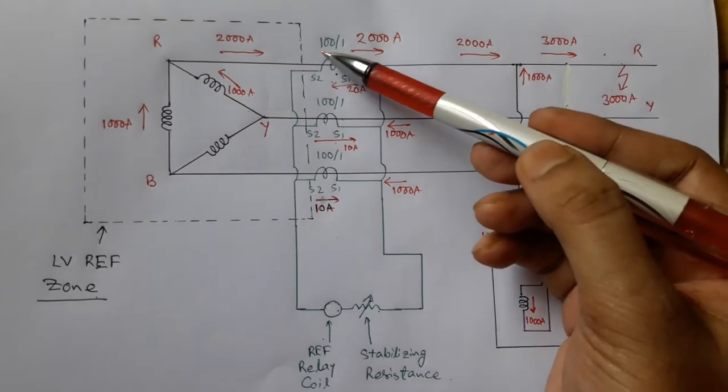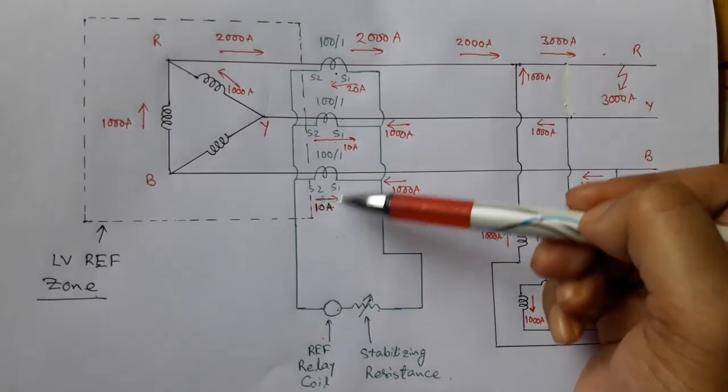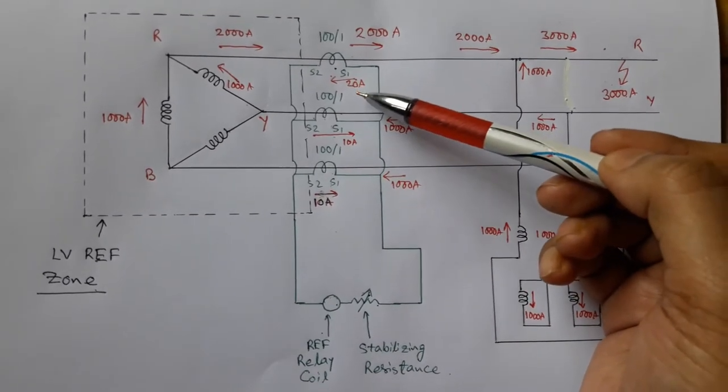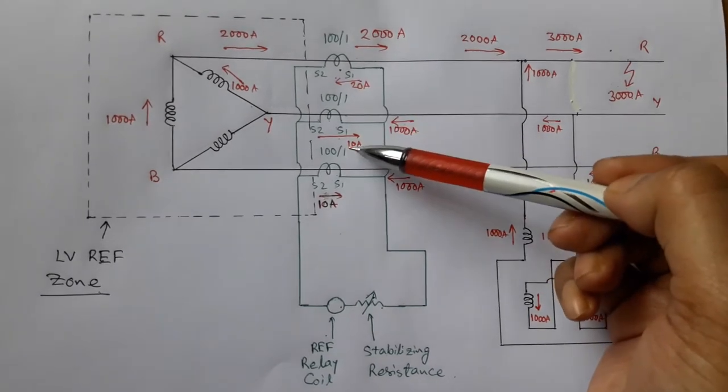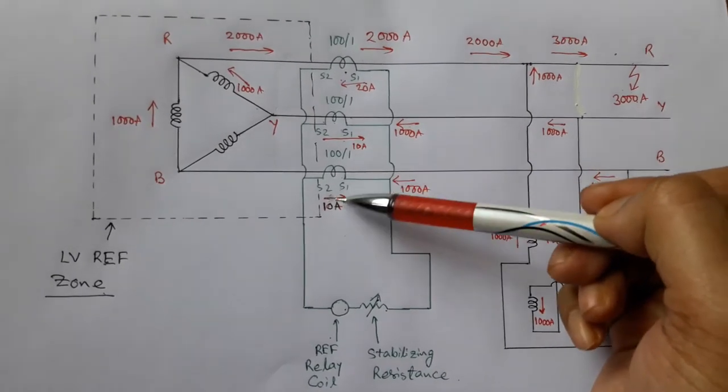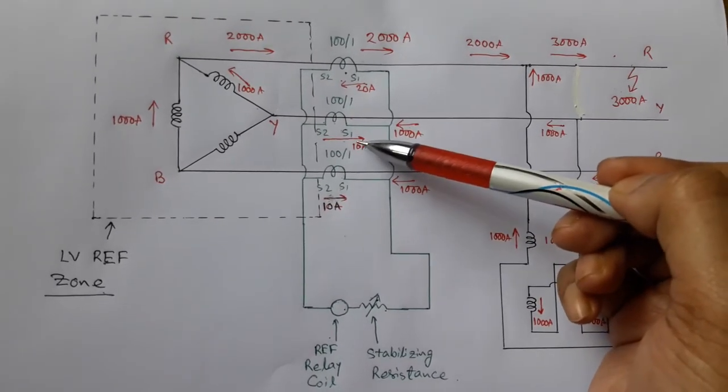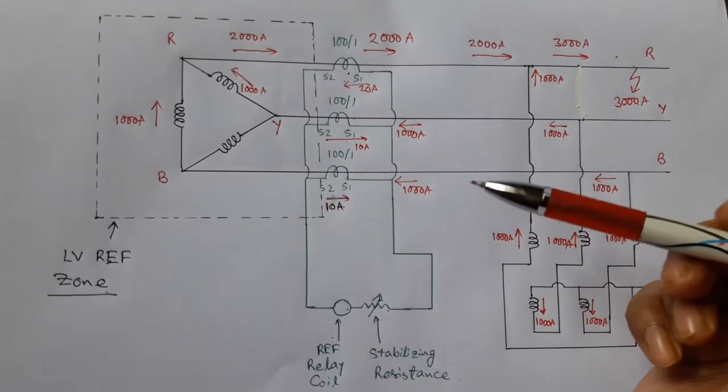As the CT ratio is 100 by 1 ampere, these are secondary values of currents. So in the case of the secondary circuit, red phase secondary current is also double the values in yellow and blue phases. And the direction of red phase secondary current is also opposite to the direction of yellow and blue phase secondary currents.